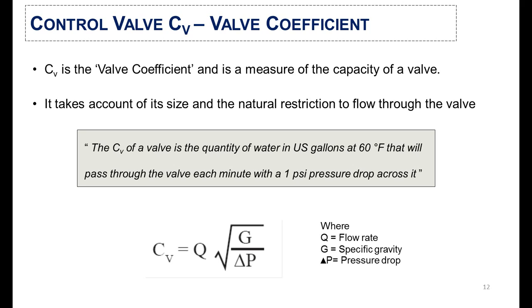The main component in control valve sizing is the valve coefficient, called Cv. The Cv is a measure of the capacity of a valve — it accounts for its size and the natural restriction to flow through the valve. Basically, the Cv of a valve is the quantity of water in US gallons at 60°F that will pass through the valve each minute with a one psi pressure drop across it. The formula to calculate Cv uses Q (flow rate), G (specific gravity), and ΔP (pressure drop).